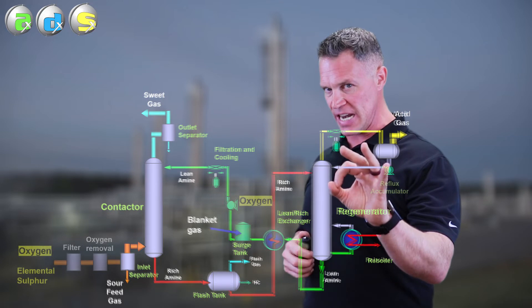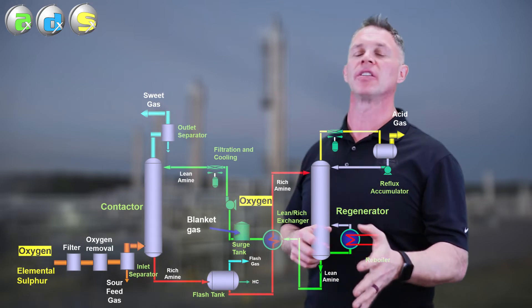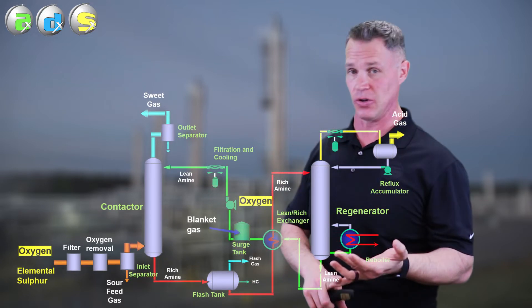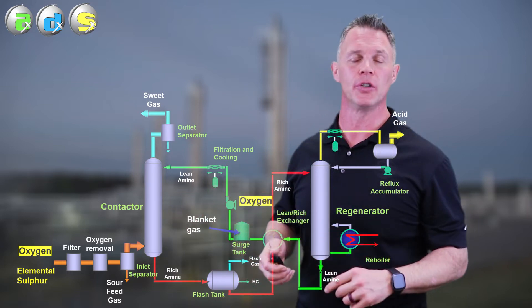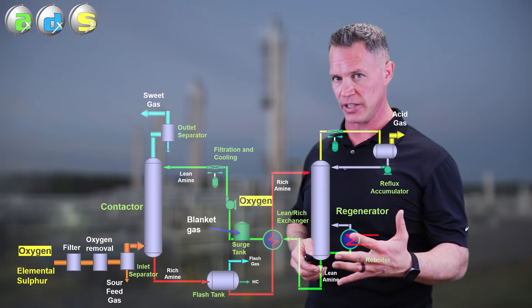If the oxygen is in your feed gas, you know it's in the feed gas because either you don't have a surge tank or you do have one and the blanket gas is on, you check the valve and it's open, then it's coming in from the feed gas.